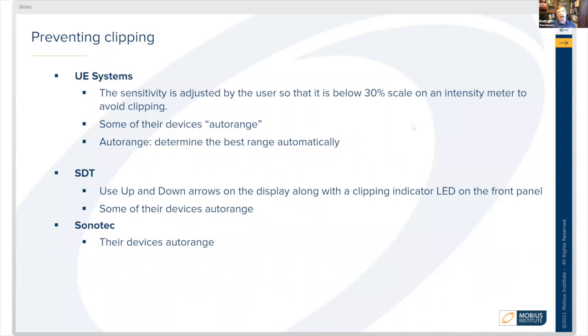Different manufacturers handle clipping differently. For UE Systems, the sensitivity is adjusted by the user, and you should adjust it so that it is below 30% scale on the intensity meter to avoid clipping. Some of their devices auto-range, determining the best range automatically.